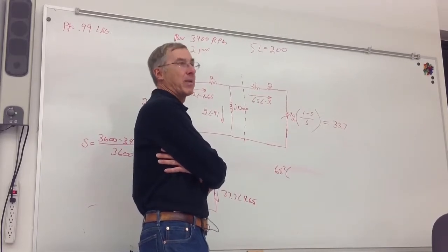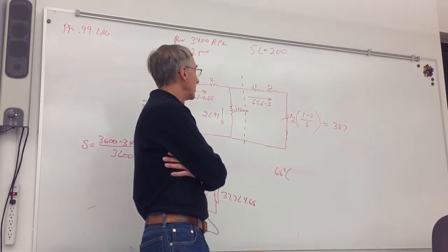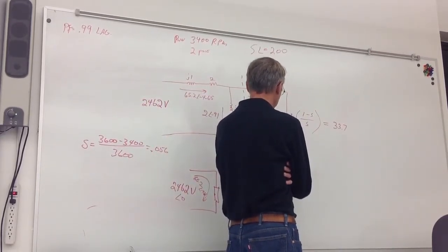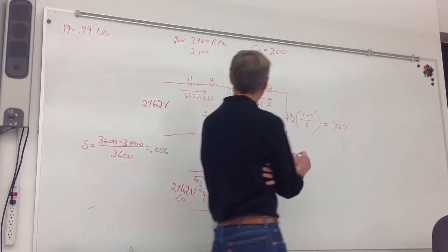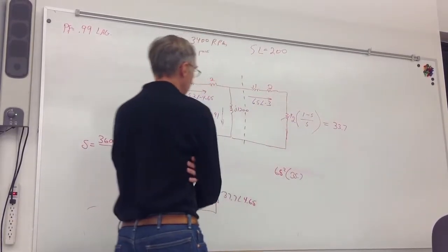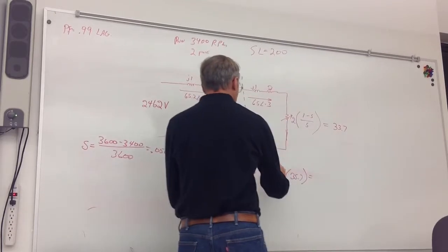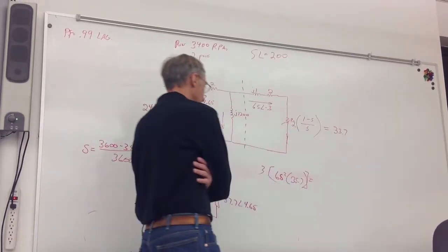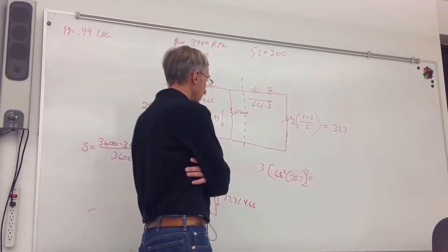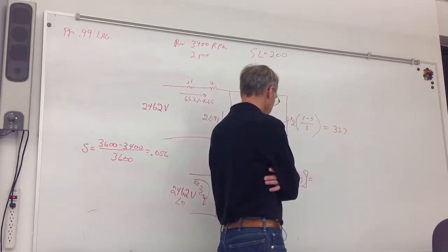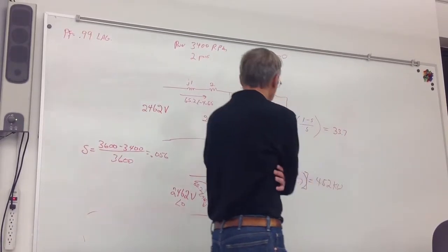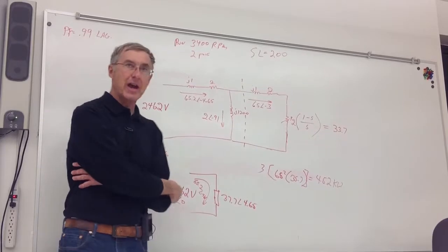We got VARs. So will that give me the real power across the air gap? Why not? It won't. R is just the 35. So what will? 65 squared times what? 35.7, or 33.7 plus 2, yes, you summed them up, that's fine. So what's my power across the air gap? And I'm going to have to multiply it by 3, three-phase machine. Watts. 452 kW.